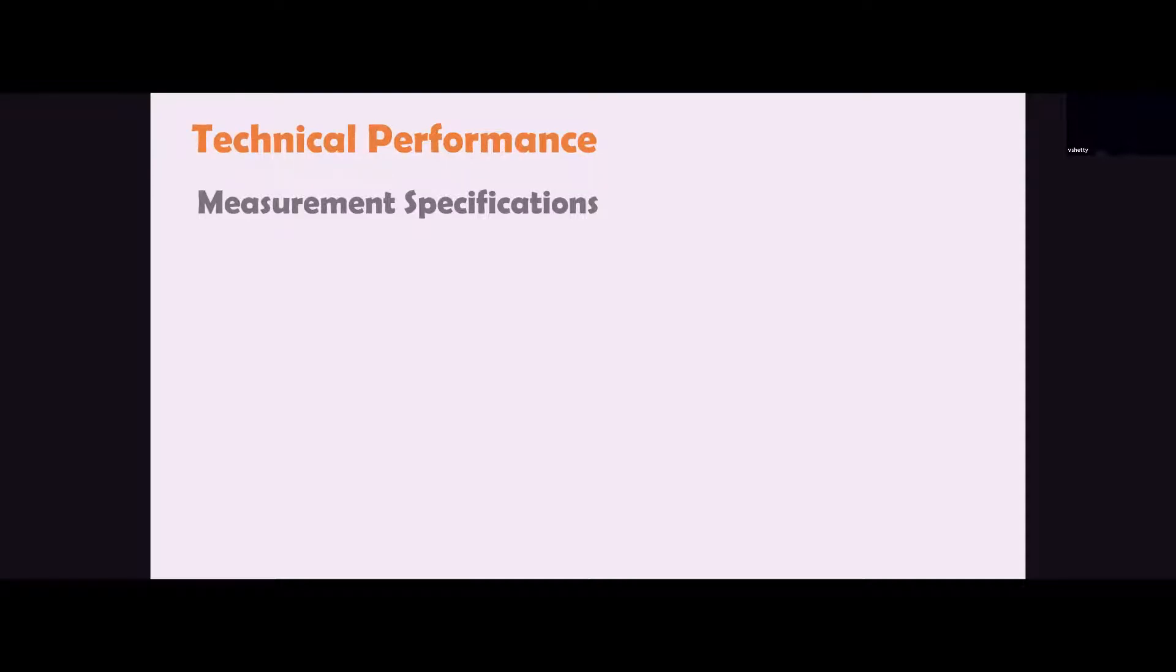Once you have defined the clinical problem and the context of use, the next step is to seek out the best technology to answer your question. In evaluating sensors, the technical performance should be a key consideration. This is usually done first through a technical verification of the sensor's measurement performance. Technical verification ensures that the sensor meets all the engineering requirements of the use case and that the sensor will provide you a reliable and accurate data collection system.